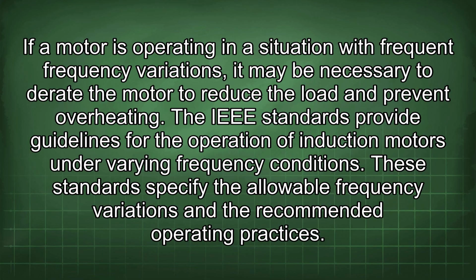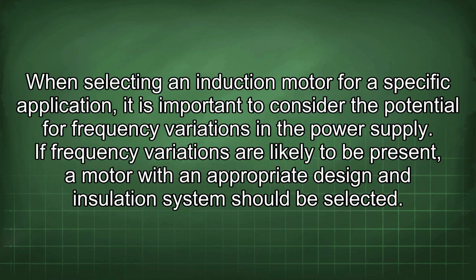The IEEE standards provide guidelines for the operation of induction motors under varying frequency conditions. These standards specify the allowable frequency variations and the recommended operating practices. When selecting an induction motor for a specific application, it is important to consider the potential for frequency variations in the power supply.